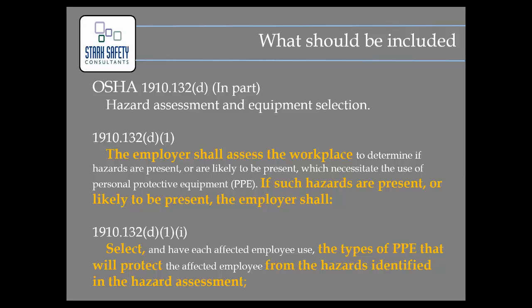So your PPE has to be based on something. Be very conscious if you use the less-than-240-volt exception in IEEE 1584, or anything above that, of what you're going to do for equipment that falls below that cutoff, and how you'll document that you've still done an assessment. We've seen people use that exception and then not address the equipment downstream of it, or even worse, just put a generic label on without doing any formal assessment.